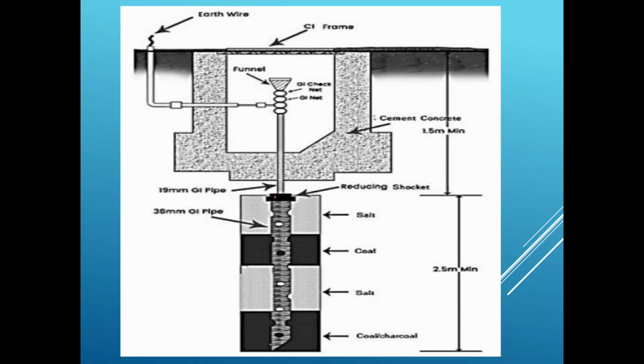In the previous case, the earth wire is physically visible in pipe earthing, whereas in plate earthing it is not physically visible — that was a drawback. Here it is an advantage, since it can be examined physically to check whether it is working properly. The only disadvantage of pipe earthing is that the pipe length has to be increased sufficiently in case of soil with high specific resistance.